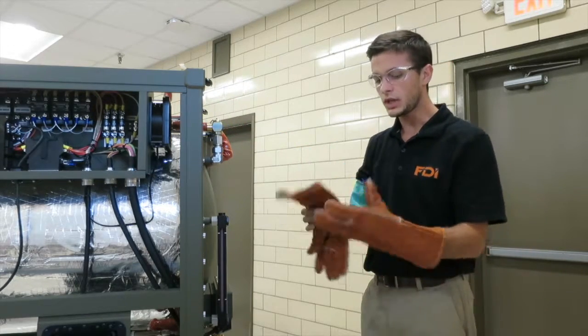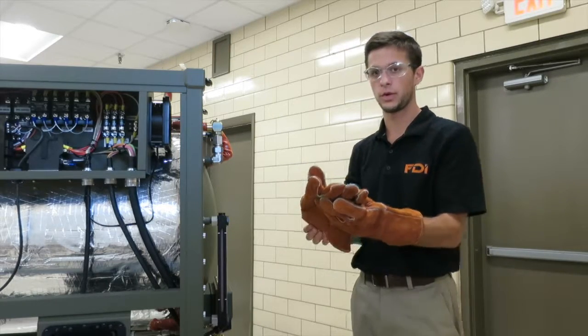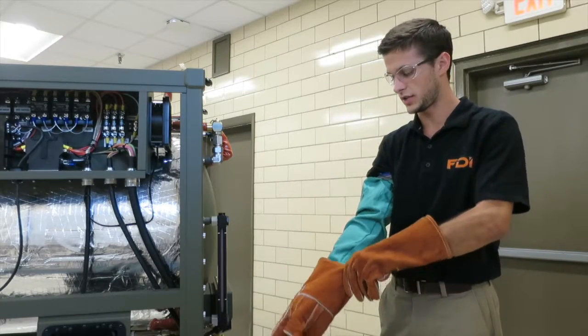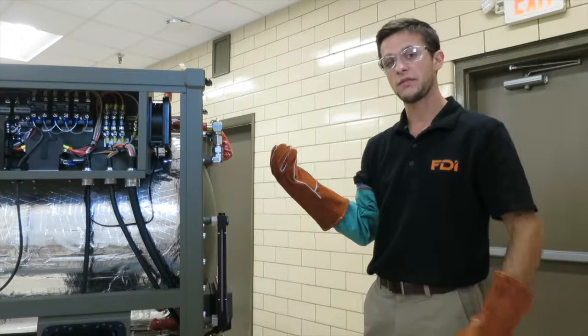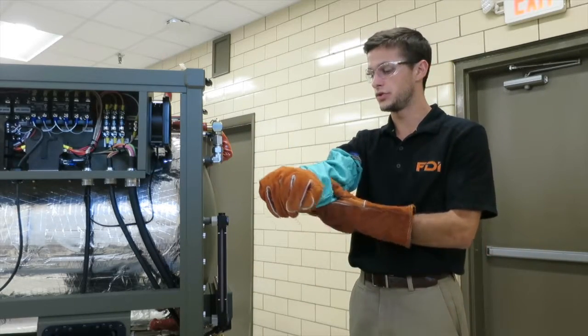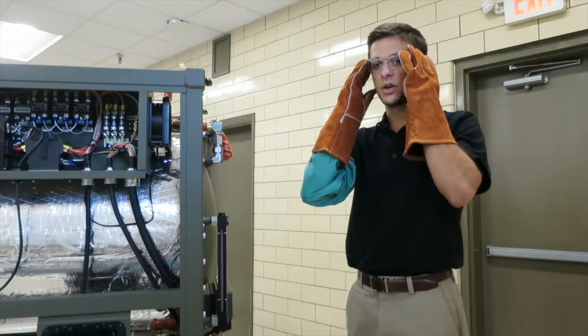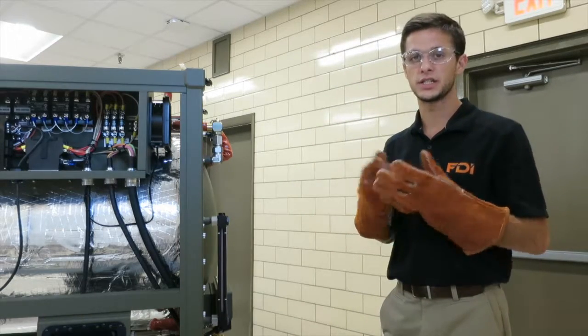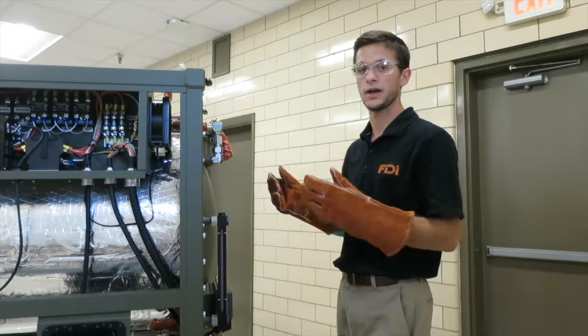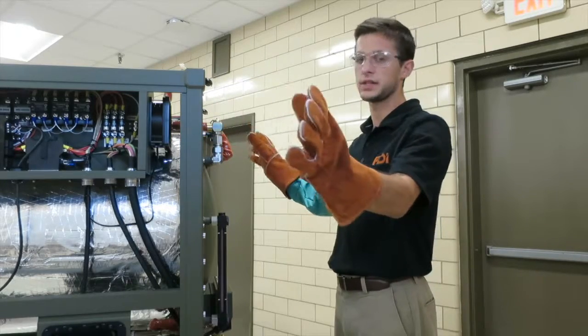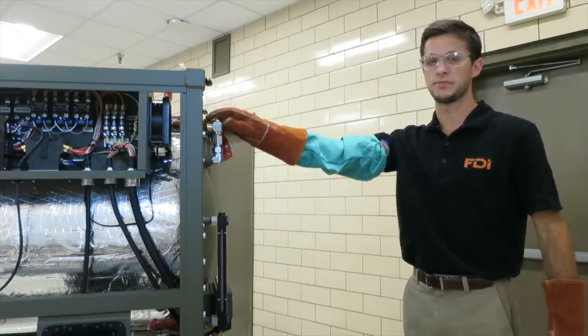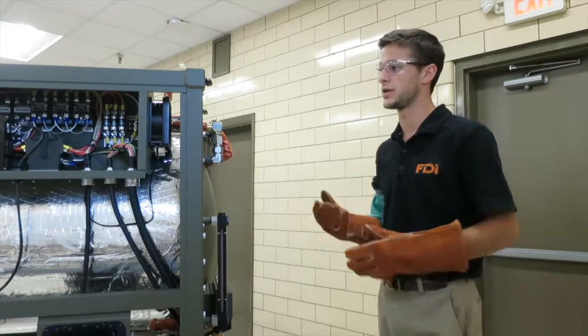So you're going to need some PPE. We're going to need some steam resistant gloves, some sterilizer gloves. If you don't have long sleeves, it's recommended that you use a sleeve, and it's also recommended that you use safety glasses, but it's not required because the steam actually shoots out to the sides. So if you're a safe distance back, the steam should never go near you.